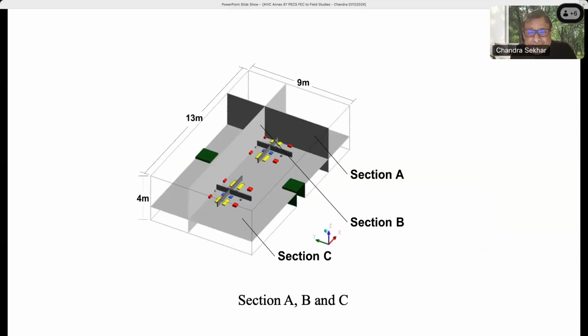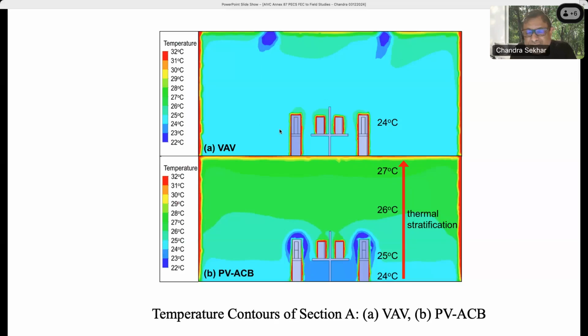We also did a CFD simulation study to show how the microenvironmental air distribution moved around. This is the kind of modular concept we were studying with CFD. The top slide is VAV, where the temperature everywhere in the room is about the same, 24 degrees. Whereas with the PV active chill beam, we let thermal stratification occur.